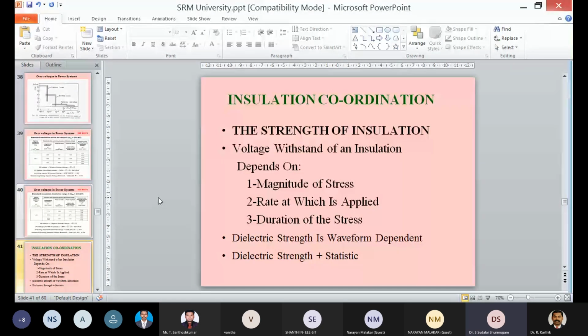So generally, this is the common case for any insulation. The strength of the insulation depends upon the magnitude of the stress, the rate at which the stress is applied, and the duration of the stress. And of course, the dielectric strength is waveform dependent. The critical part here is that it is necessary to provide enough insulation, but over-insulation results in extra cost to the utility, while under-insulation, or poor insulation coordination, results in poor supply reliability. So we always have to match a secure supply with minimal cost.